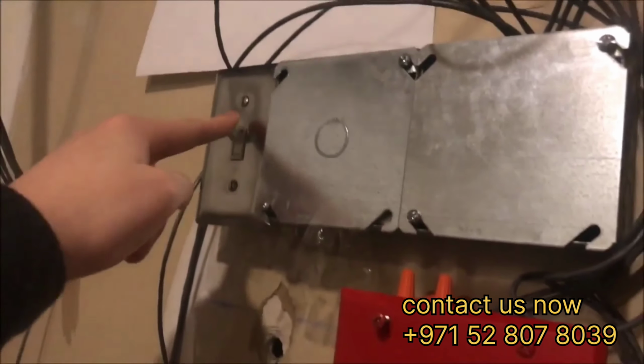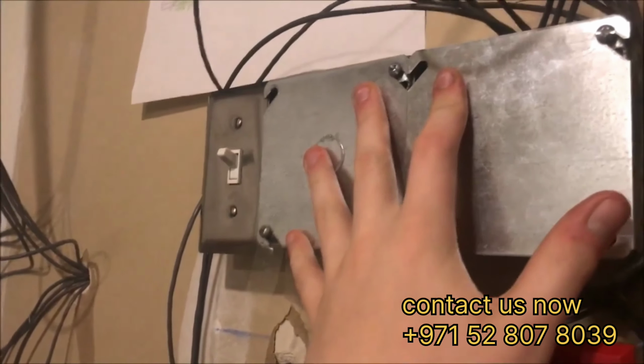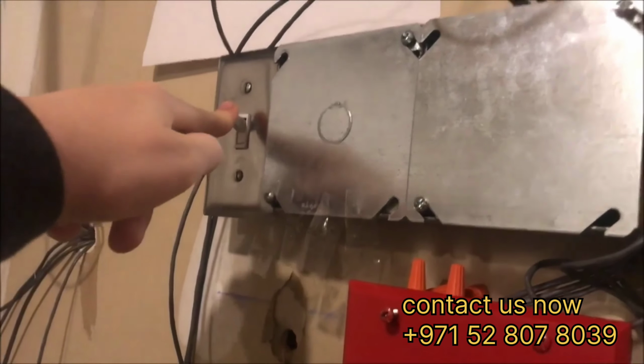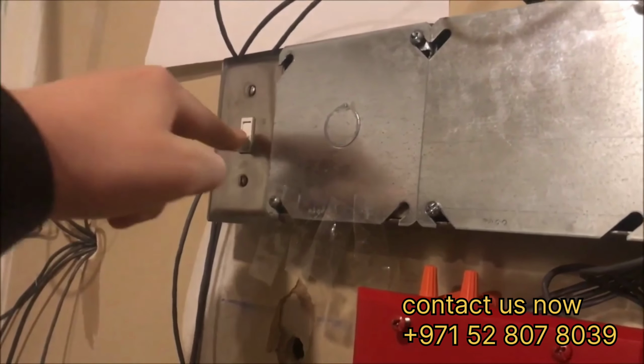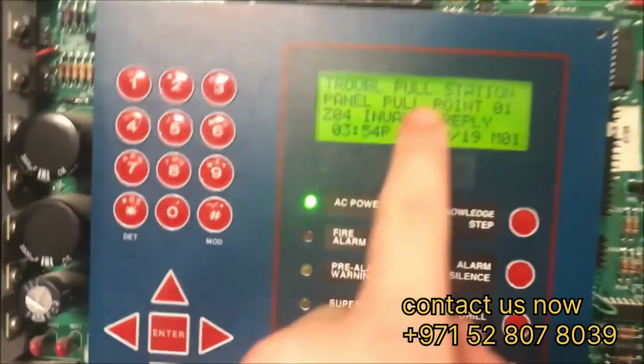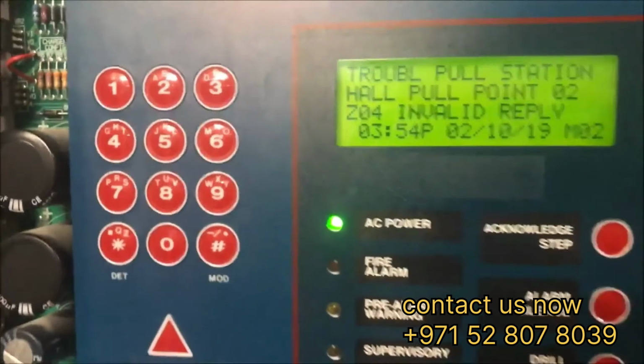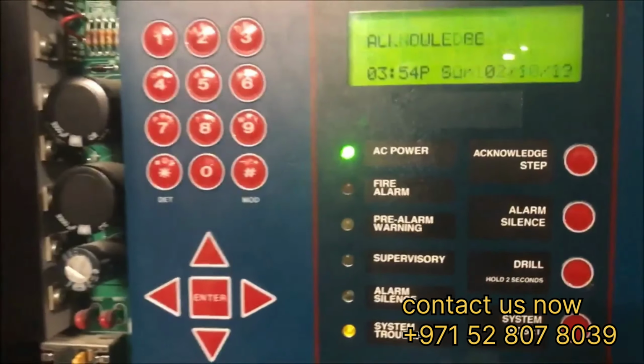So if I go back and I shut off my SLC to my Notifier panel, so this is my SLC shut off. Basically what it does is there's a whole bunch of modules in here. This disconnects the power going to them so I can service the panel. So if I disconnect that, I go into trouble and it's telling me invalid reply, meaning it can't hear that module anymore.